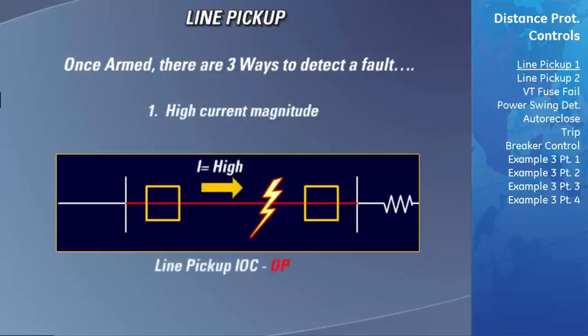The first method the line pickup element uses to detect a breaker closing in on a fault is by using an instantaneous overcurrent element that is built into the line pickup scheme. If the line pickup element detects that the magnitude of the current has risen above the pickup level of this IOC element, it indicates that the current is not flowing to a load but instead to a fault. Therefore, the pickup level of this element must be set higher than the maximum amount of current that will be seen during normal inrush conditions. Please note that this line pickup element is different than the normal IOC element that is available in the D60. This line pickup overcurrent element will only be used once the line pickup element has been armed.